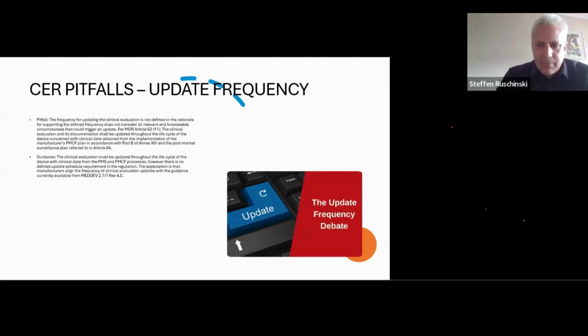2.7/1 Revision 4. And based on this guidance, the clinical evaluation should be updated minimum when the manufacturer receives PMS, including PMCF information, which has potential to change the current evaluation. It has to be updated at least annually if the device carries significant risks or if it is not well established. Otherwise, it has to be at least updated every 2 to 5 years if the device is not expected to carry significant risks and it's well established.